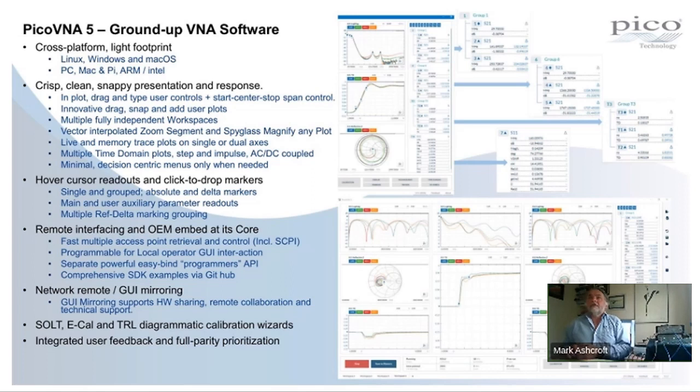Part of SCPI supports local remote interaction, so you can have an automatic program running setups and then an operator interacting with the GUI using the SCPI interface. Of course, the SCPI interface is very common amongst all our competitors. There's a lot of automatic programming material that has already been generated with SCPI-like commands, and here the change to PicoVNA5 is fairly straightforward.